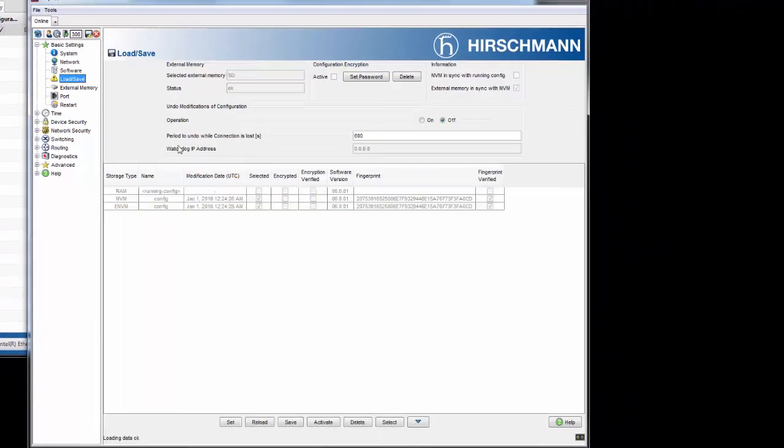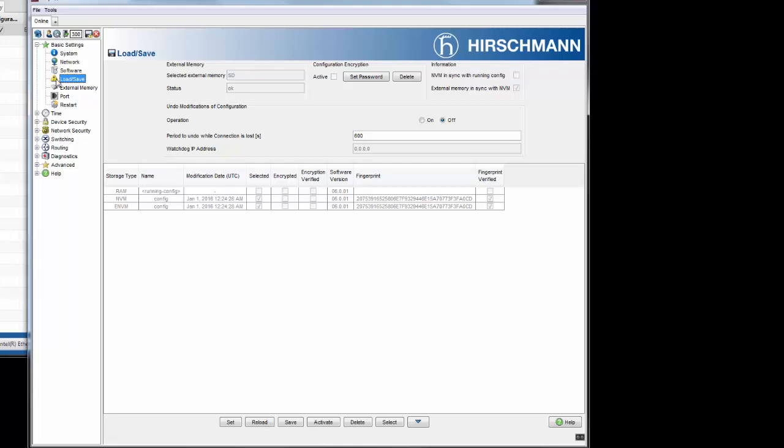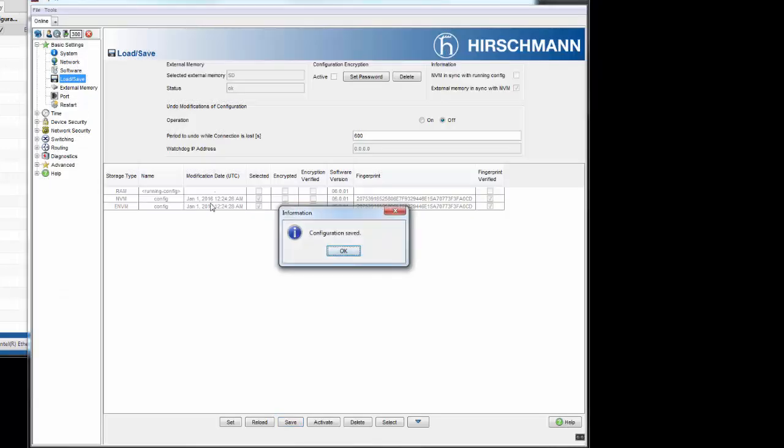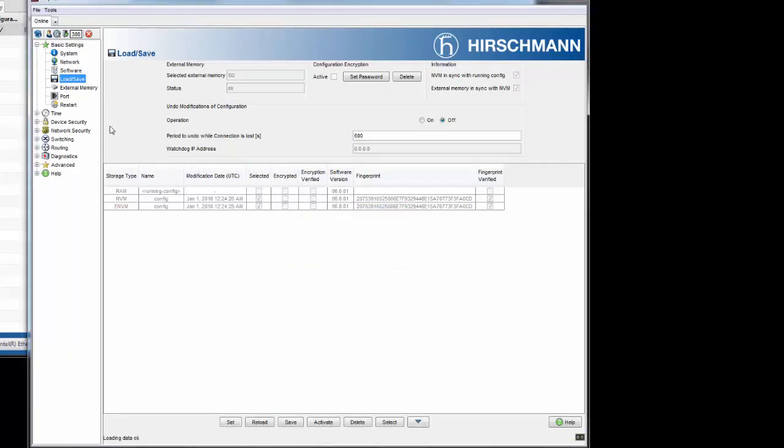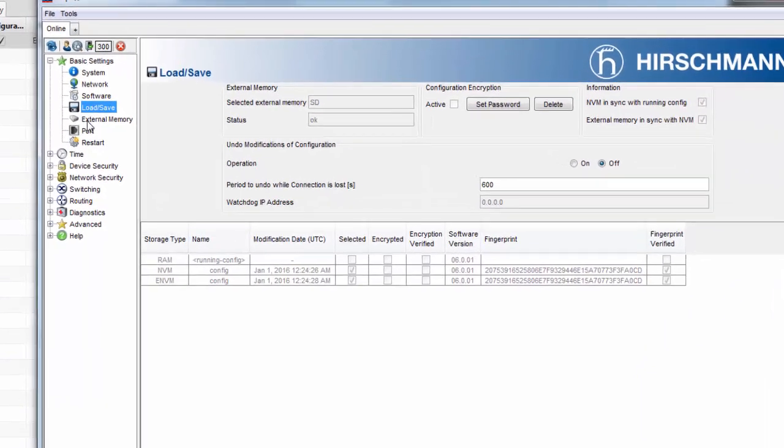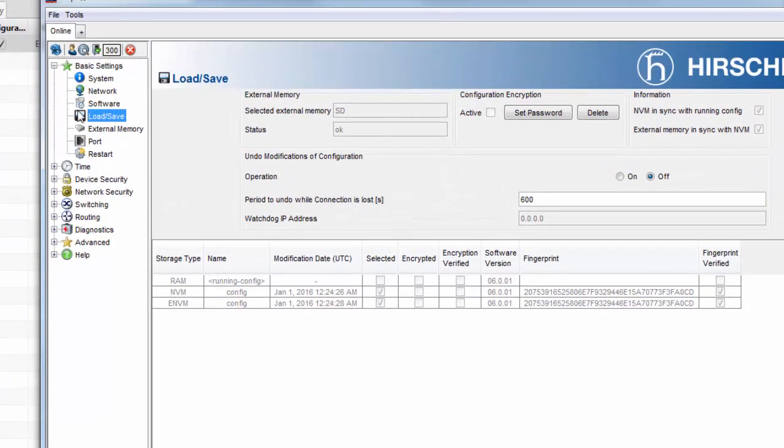So to ensure that this IP address is saved and converted from volatile memory, I'm now going to save it to the non-volatile memory. I will now click on save. As I do this, it's taking all the configurations that I've done and saving them to non-volatile memory. You'll notice that the warning triangle is now gone.